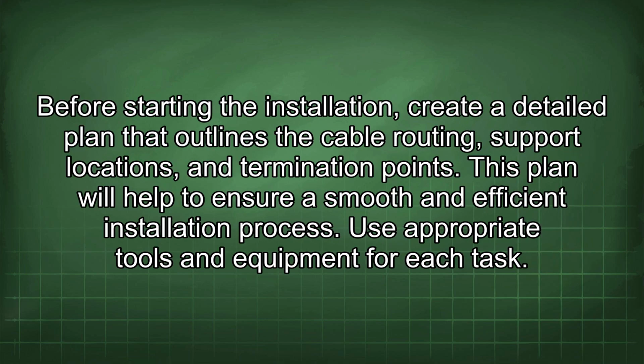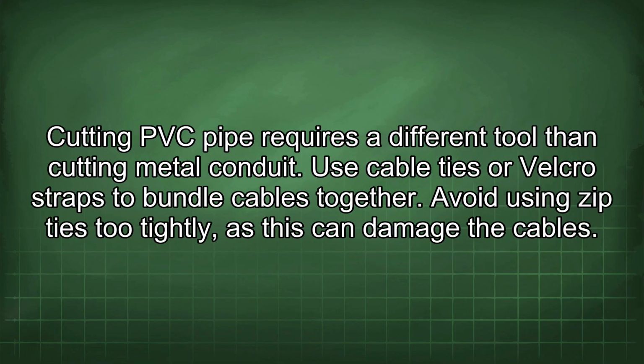Before starting the installation, create a detailed plan that outlines the cable routing, support locations, and termination points. This plan will help to ensure a smooth and efficient installation process. Use appropriate tools and equipment for each task. Cutting PVC pipe requires a different tool than cutting metal conduit. Use cable ties or Velcro straps to bundle cables together. Avoid using zip ties too tightly, as this can damage the cables.